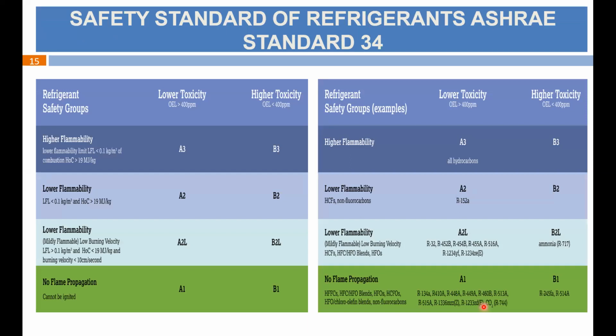This is a very important slide. Let's talk about the safety standard as per ASHRAE 34. Apart from the environmental effects, ODP and GWP, which I have covered, now let's talk about the safety of the refrigerant. In safety, two parameters are taken into consideration: one is toxicity and the other is flammability. Toxicity is given in terms of OEL, the occupational exposure limit, up to which the exposure to this refrigerant is permissible.